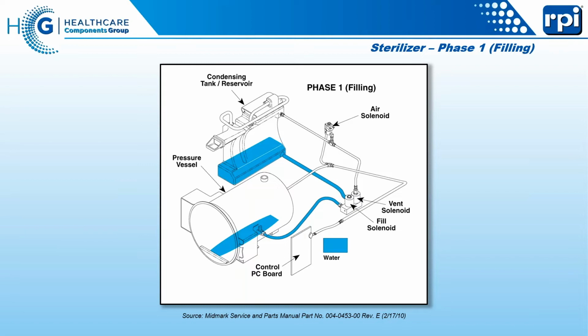So what are we talking about in running this machine? Well, while I was talking, the machine went through phase 1, which is the filling process. We let water out of the reservoir by opening the fill solenoid into the chamber. Now in the back of the chamber, there is a water level sensor. And when that water level sensor becomes conductive to case ground, the valve is closed because there is enough water within the chamber to complete a cycle.